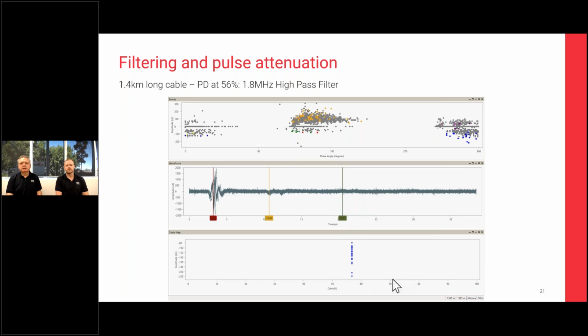But in this particular instance, we can just about see it. So for a paper-lead cable, 1.4 kilometers, relatively clean, we're just starting to hit the sort of limits. This was using an older CT, so nowadays we can see quite a bit further than that with the best CTs that we have, but that's still looking at the sort of lengths that you're starting to hit with paper-lead cables.